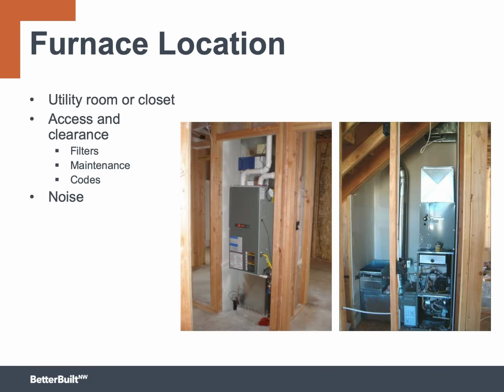The key with these spaces inside a house will be to make sure that you've got adequate clearance for general maintenance, filter changes, and that kind of thing. Be careful that you understand what the codes are and the local interpretation of those codes before you start squeezing all this equipment into a very tight space. Because floor area is expensive, you may be tempted to reduce the size of this mechanical space as much as possible, but you still need to make sure that it's not too small and everything will fit well. Don't forget that we're also talking about vertical space, not just horizontal. Especially if you're going to have filter racks and air conditioning coils, be sure there's enough height to accommodate those.